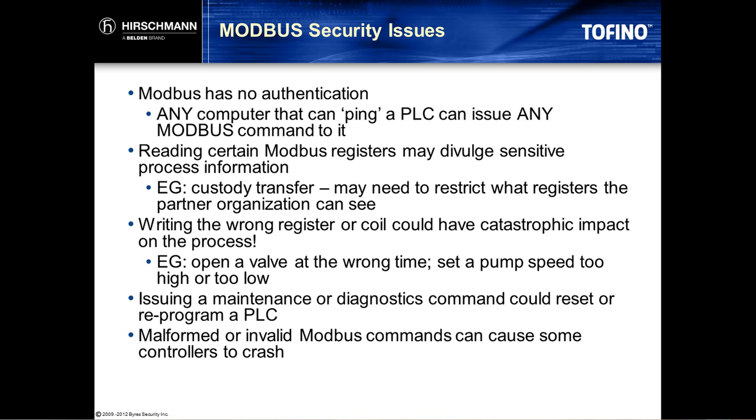In addition, many brands of industrial controllers use the Modbus protocol to transport maintenance and diagnostic commands. For example, many of them allow you to upload new ladder logic to the device. You can set the device into test modes. There's all kinds of things you can do accidentally or maliciously to a Modbus controller.